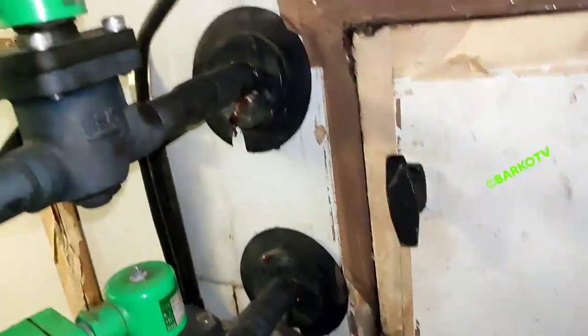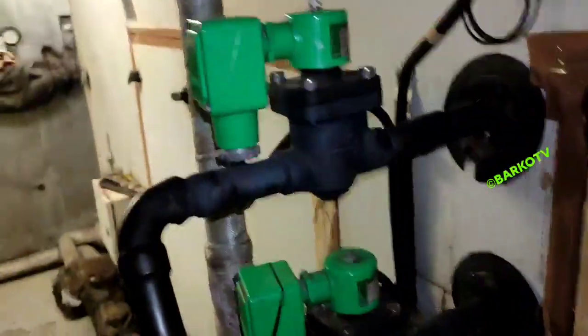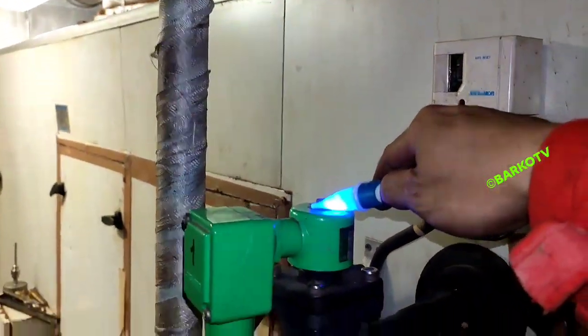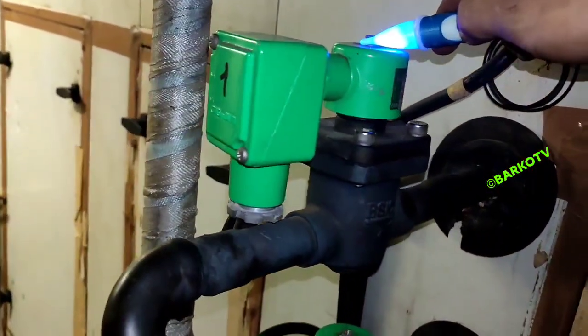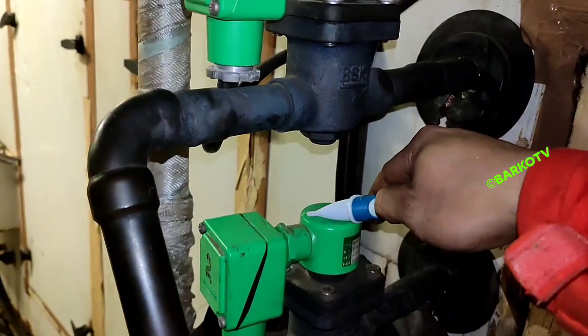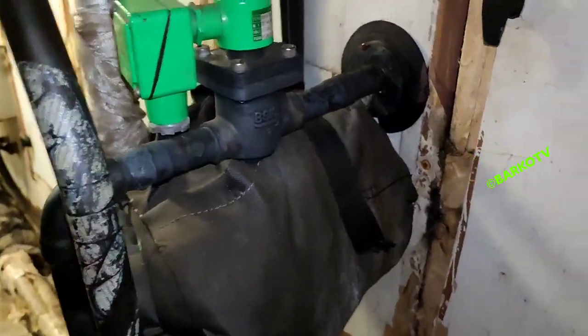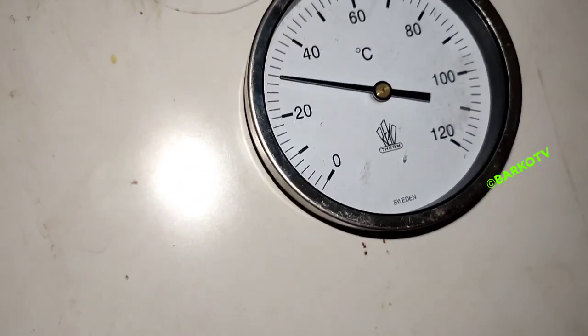We have already finished cleaning and we check the solenoid valve. It is open, meaning there is flow going to that evaporator. Solenoid valves one and two are both open.